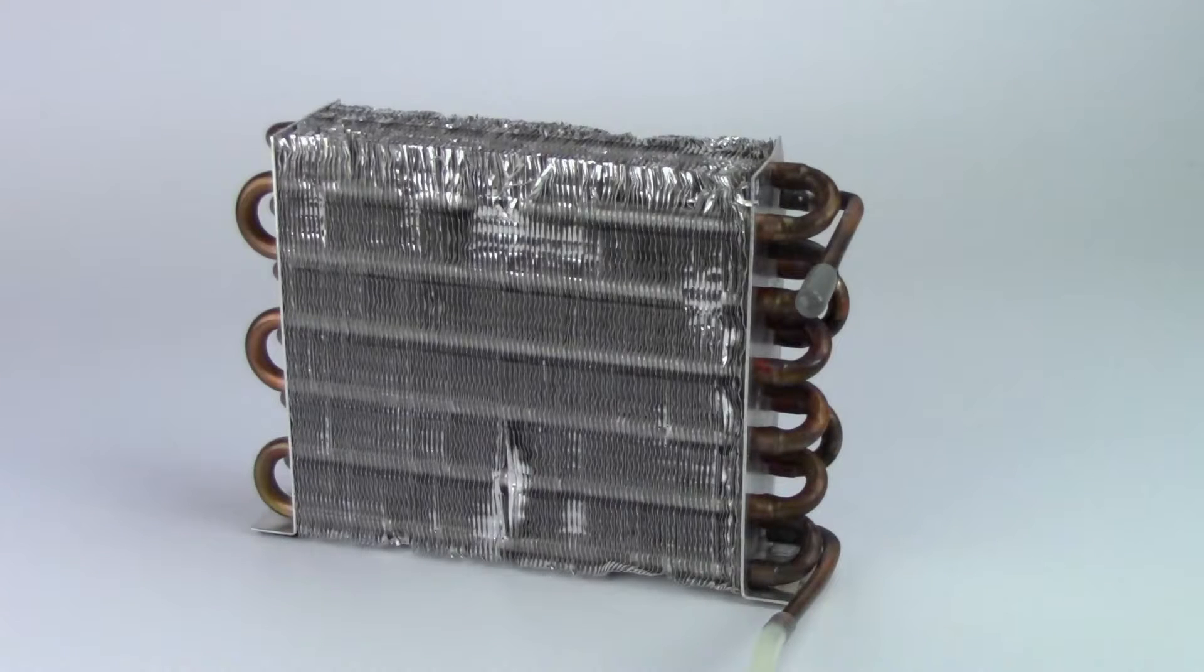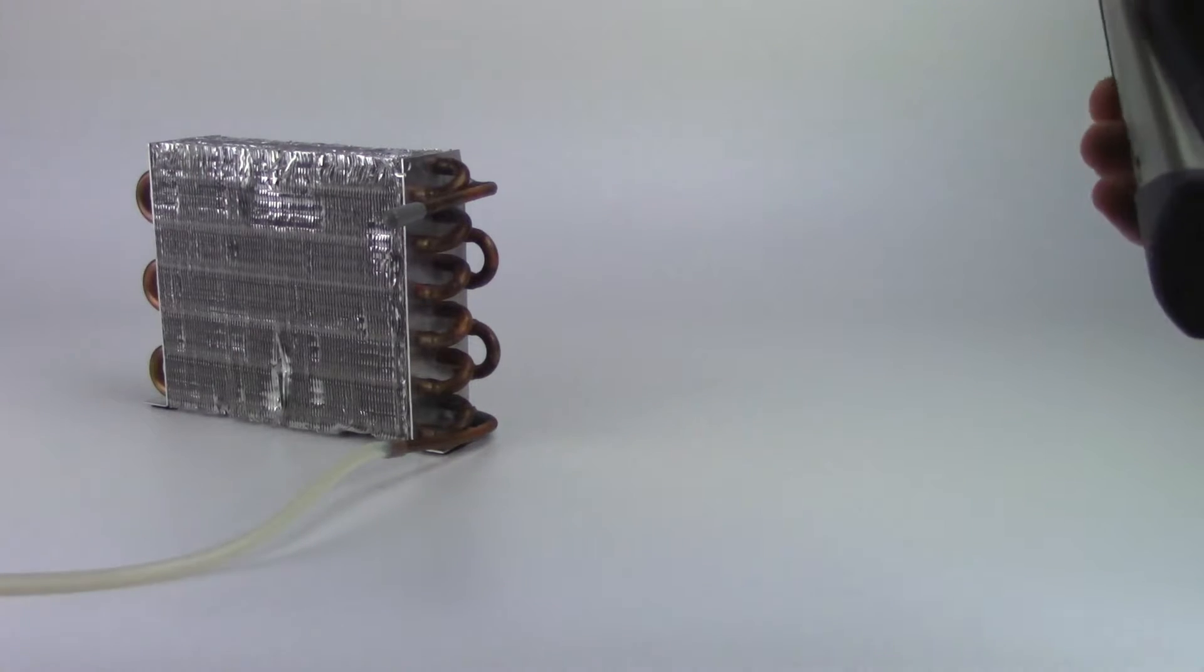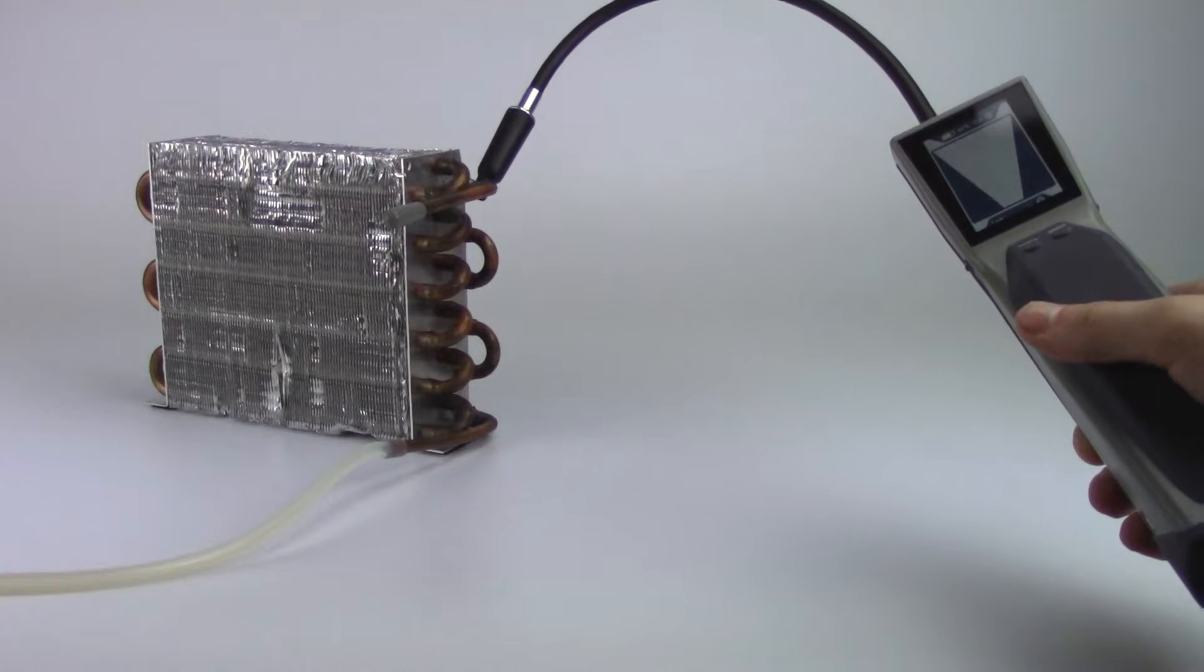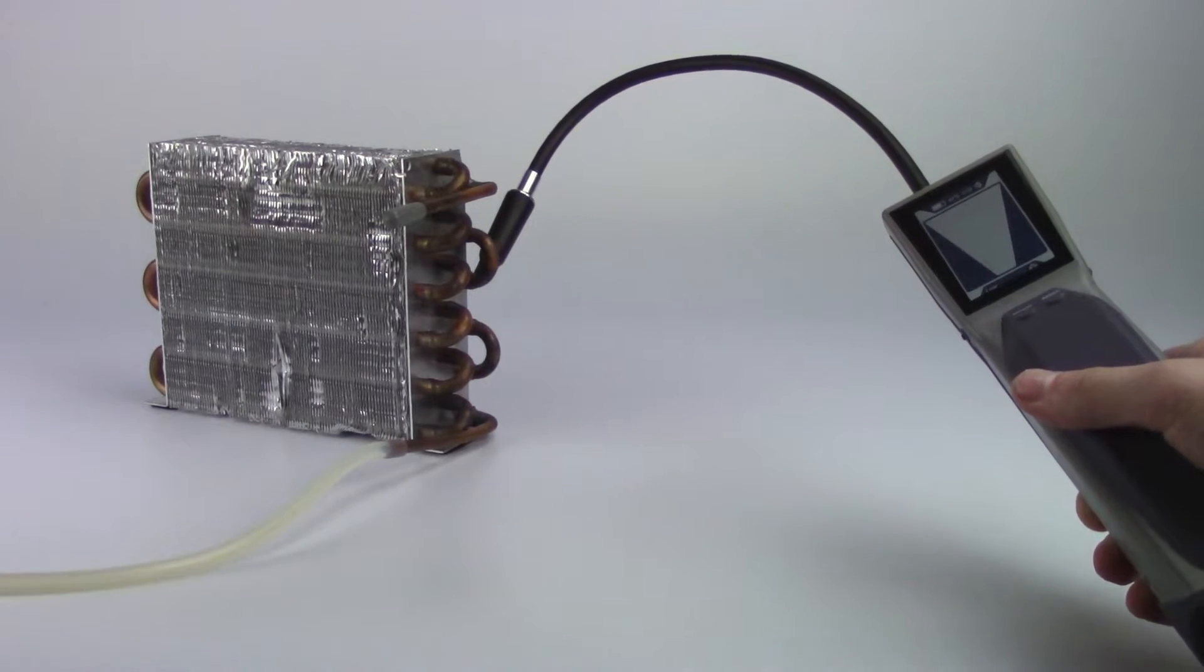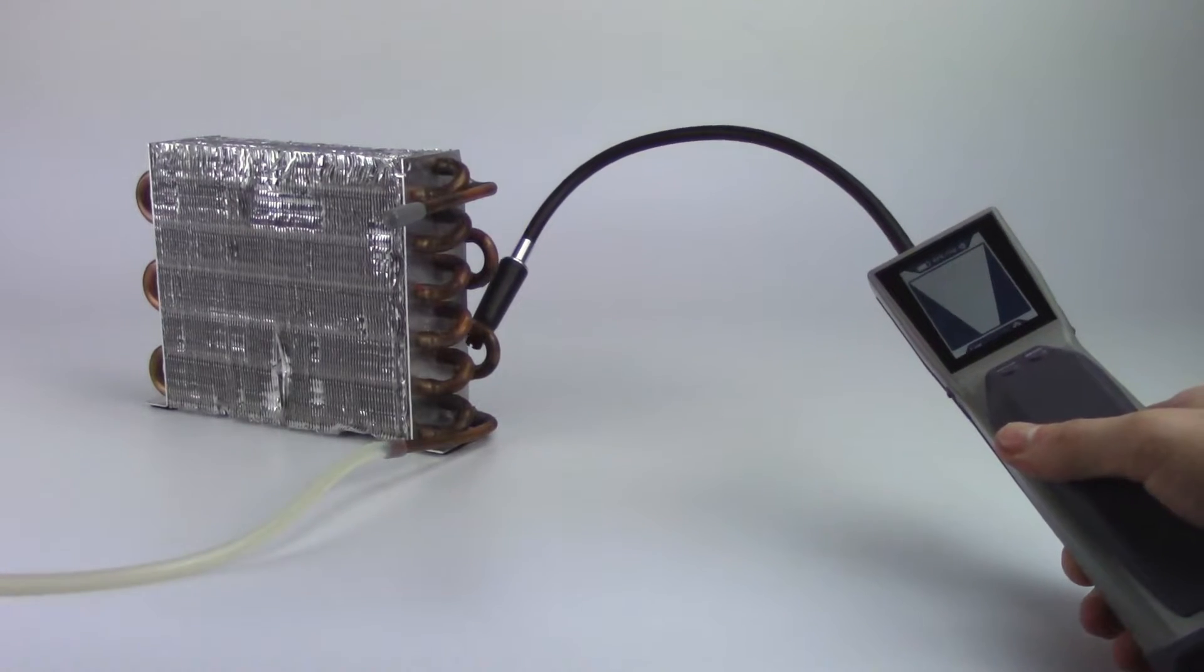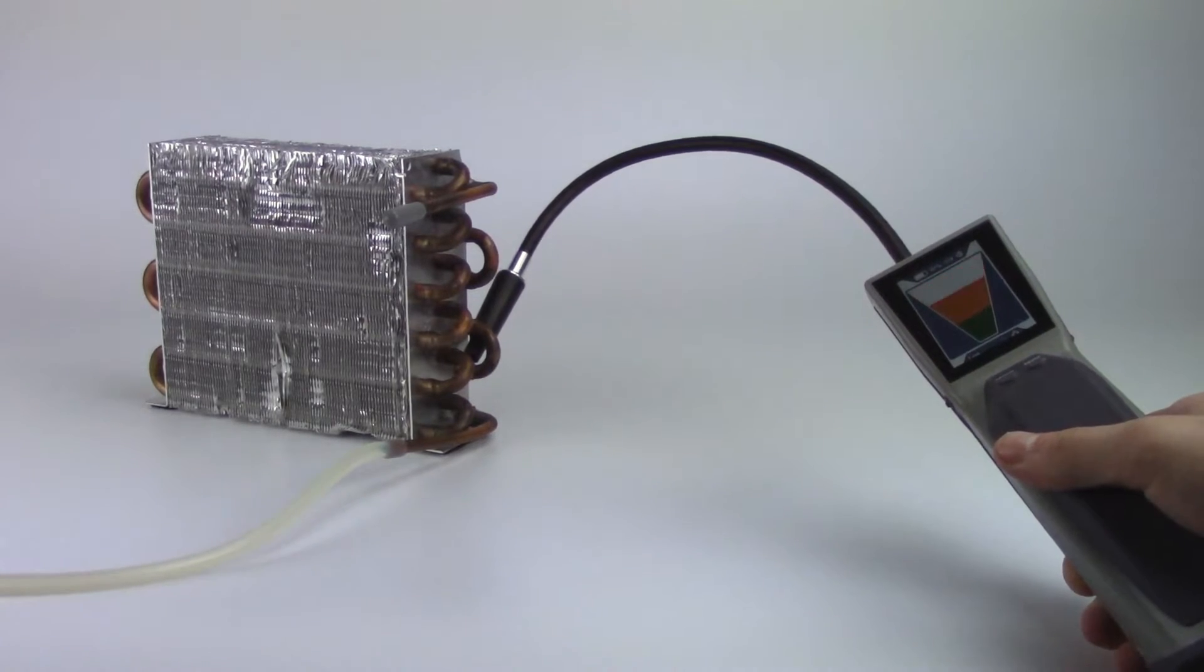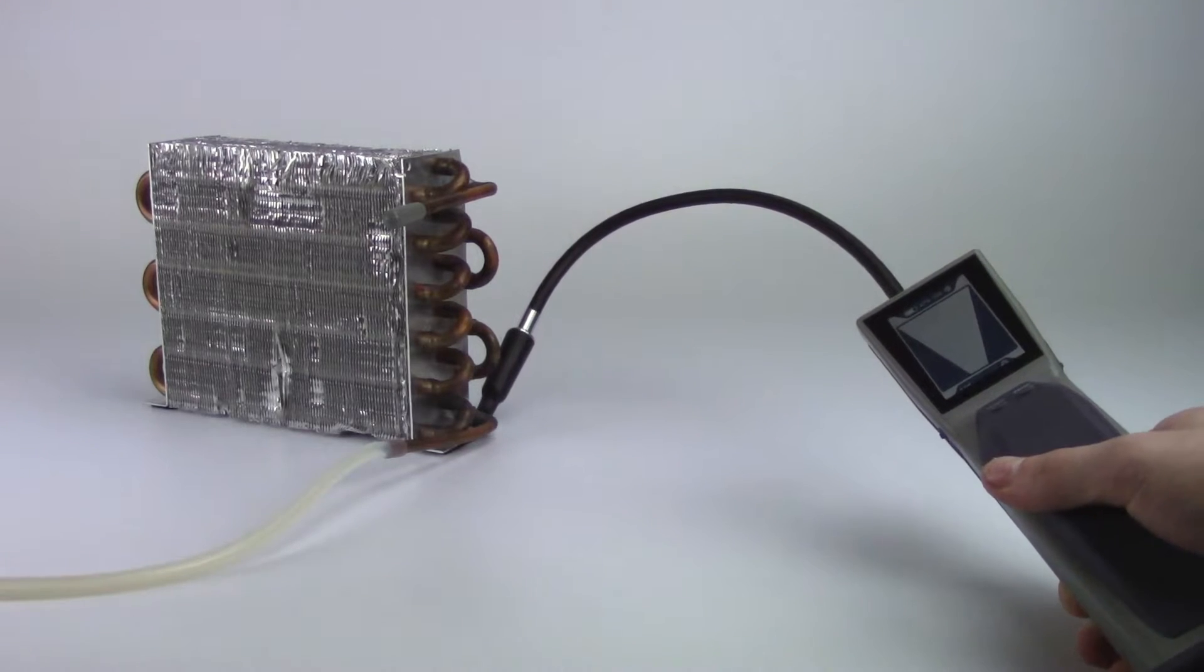In pinpoint mode, place the tip of DTEK Stratus as close as possible to the suspected leak. Do not block the airflow. Slowly move the probe past each possible leak point. If a leak is detected, DTEK Stratus will alarm and the screen indicators will illuminate.